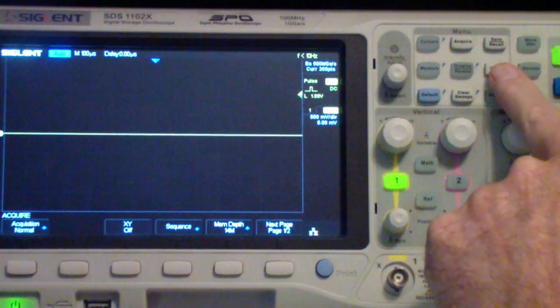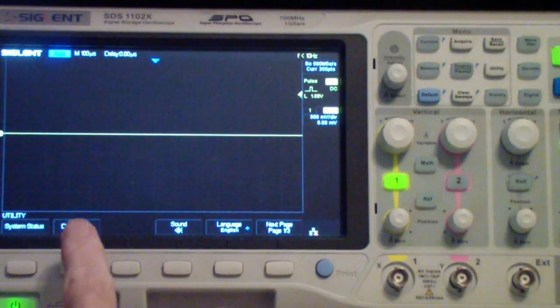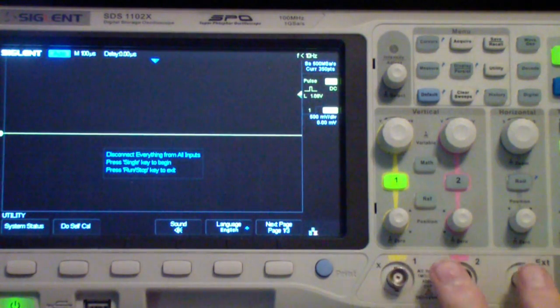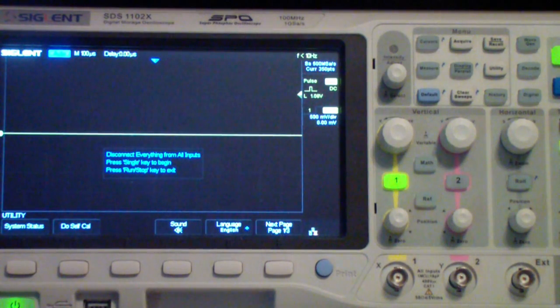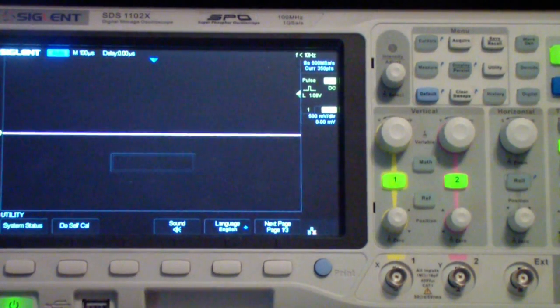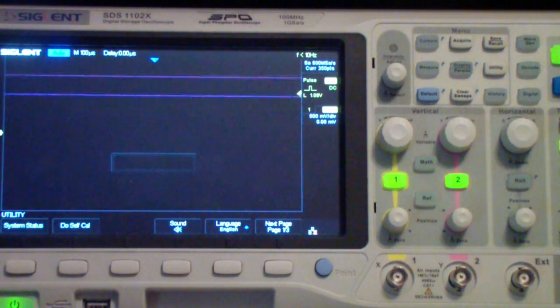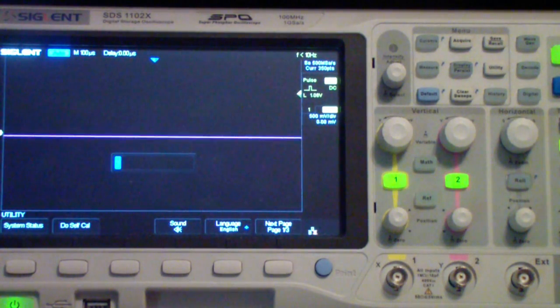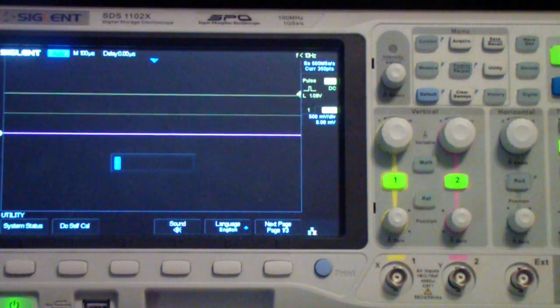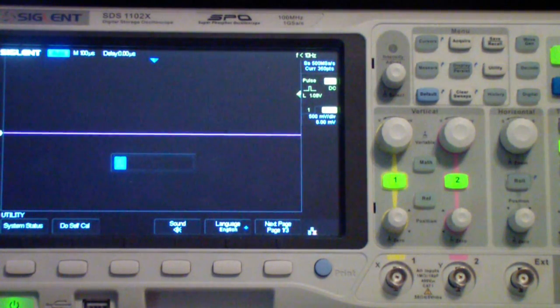The first thing we do is we go to the utility menu and then down here where it says do self cal, press that and it tells us to disconnect everything which I've done and then to press single which is the acquire button over here or trigger button and it begins to do the calibration. Now, I won't bore you with watching it go through all of this, but just notice that one of the things it's doing is it's moving each channel through its range and it does this many many times. But for now, I'm going to pause the video.